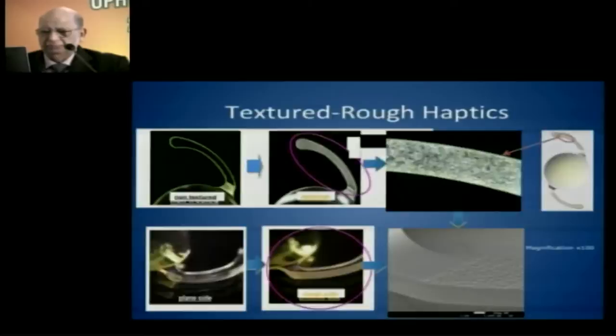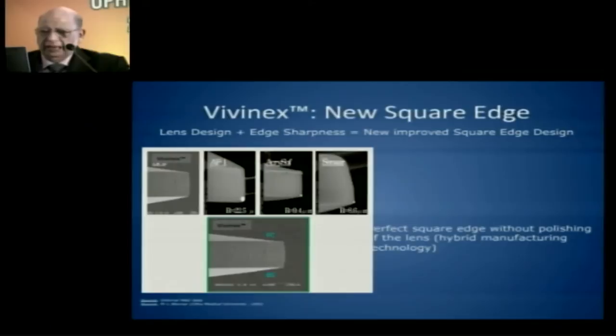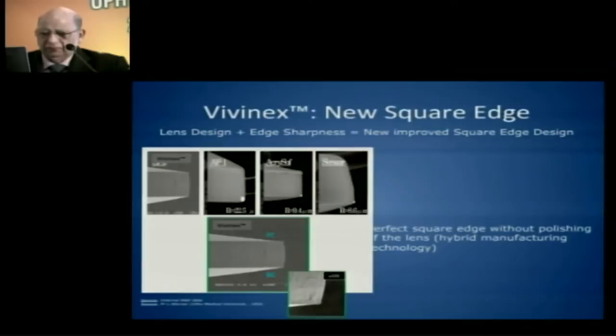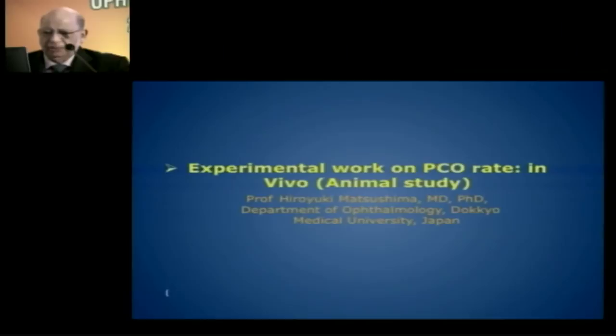PCO is also diminished by the edge sharpness of the lens design, which is a little different from earlier approaches. In earlier days, when we were worried about PCO we made edges sharp, but patients then experienced a ring reflection at the side. This has been eliminated by a blended edge design, which retains the advantages of sharpness and damming of PCO growth, without the reflection problems. The texturing of the optic edge also reduces dysphotopsia.